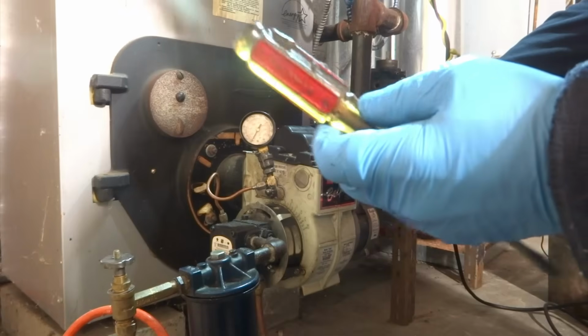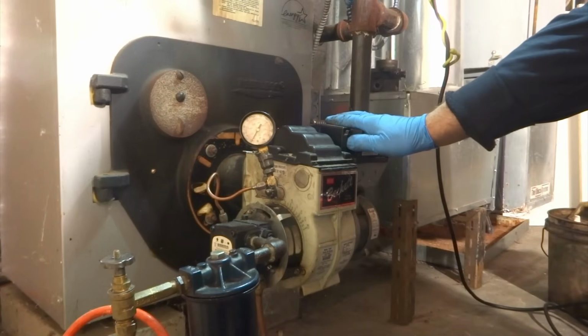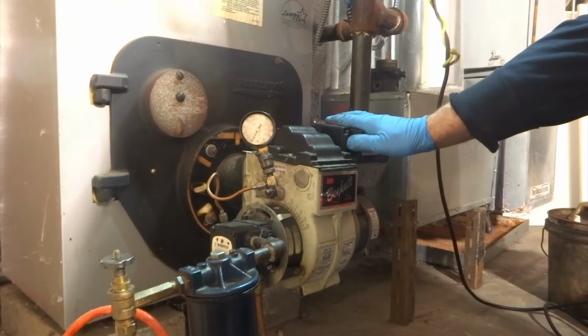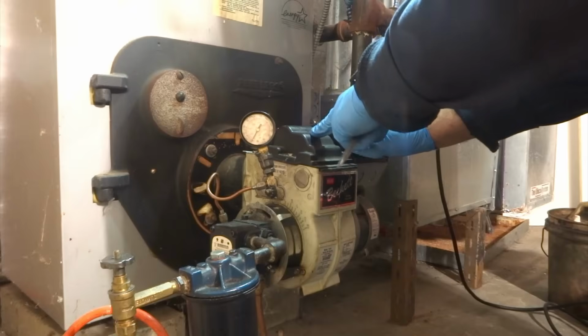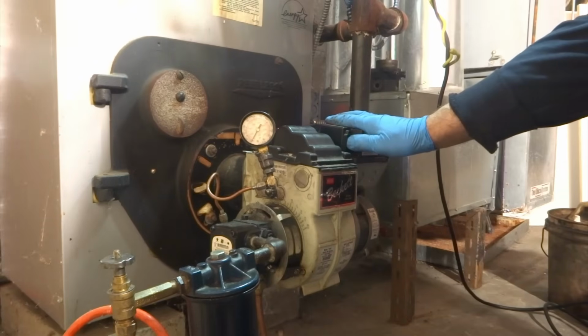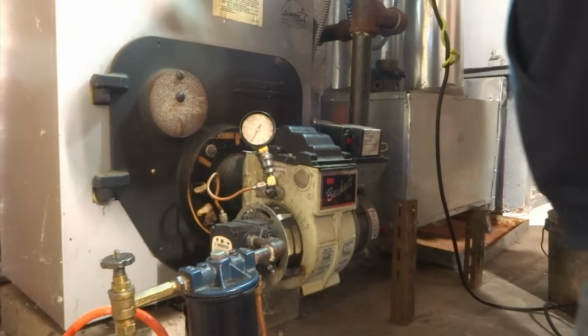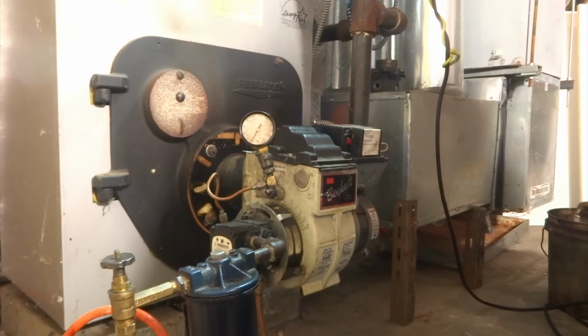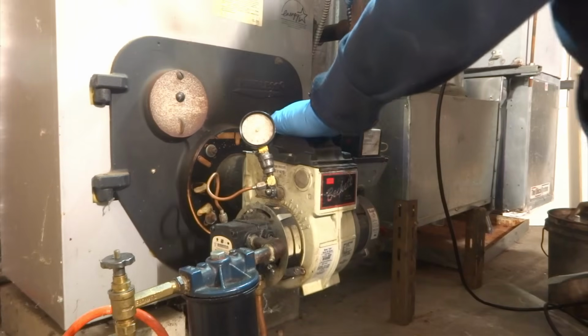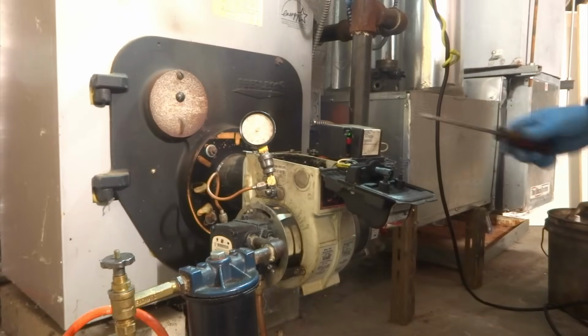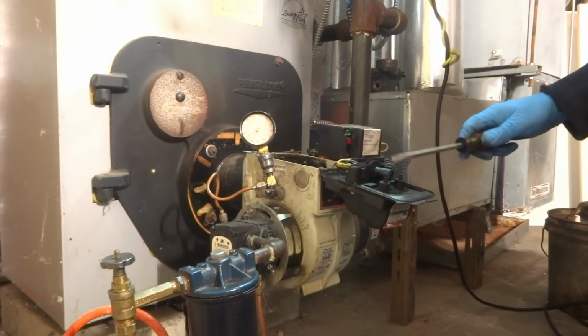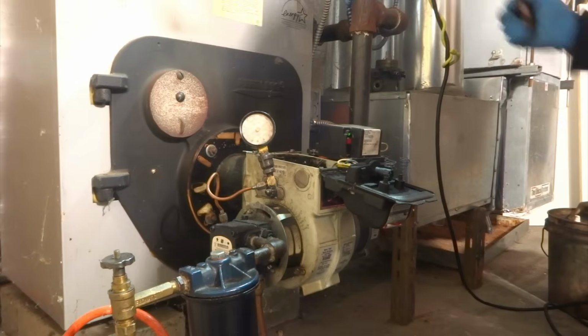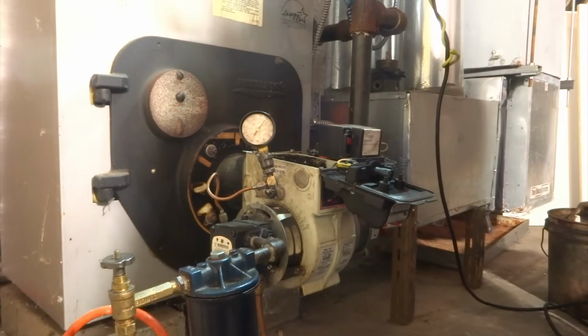Got a good screwdriver here that I don't get shocked with. Got to hold it till that flashes green, then I could release it and it should start, and then I could flip this open and check the spark. All right, there it goes. Yeah, we got a bad transformer there. No spark. See it? That's our problem. Look at a bad transformer.